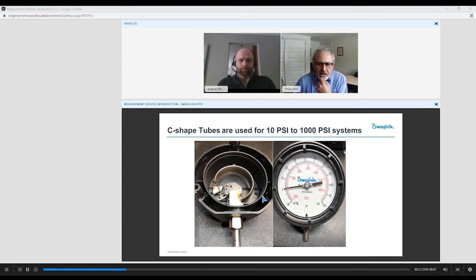And just one other thing that I'll point out, these gauges have a solid front. So if there is a failure in the system, a catastrophic failure, where the Bourdon tube has been compromised or something else, the media, it's designed so that the back will pop off. It's not going to come out through the front where the operator or someone may be there looking at the gauge. So these safety features are built in. This has a solid front. It's a thermoplastic case, used a lot in chemical plants, power plants, and pulp and paper. Most industries will use these types of gauges.